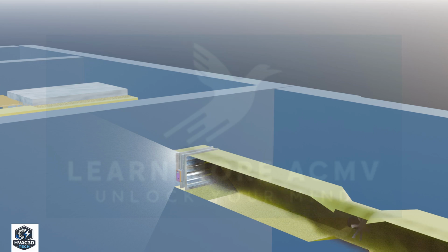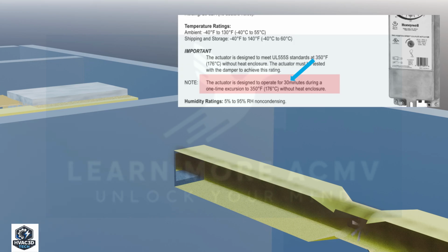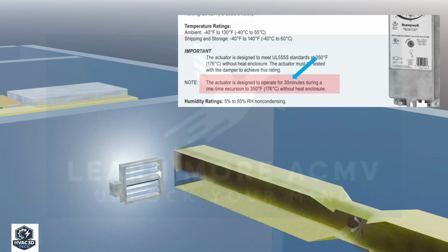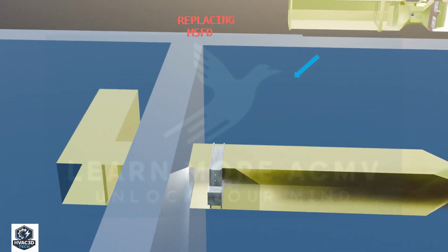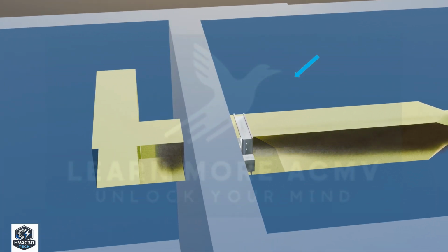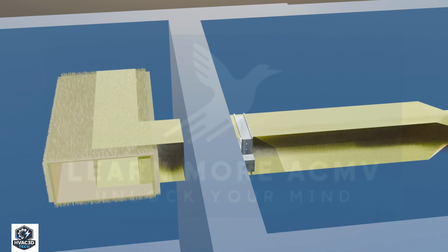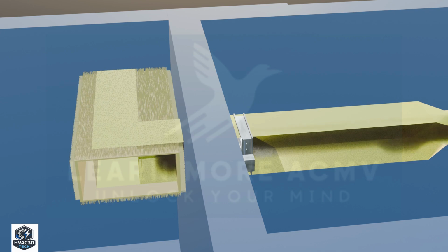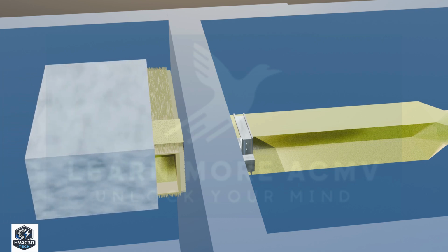Therefore, MSFD is used in the smoke control system to ensure that the smoke fan can operate reliably in both normal and fire modes. If smoke ducts penetrate from one compartment to another, meaning from one room to another, the ductwork must be fire-rated. This is because fire can spread between rooms through the duct, therefore, the duct shall provide fire protection for up to 2 hours.